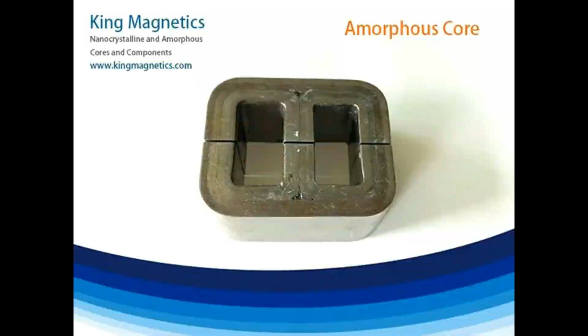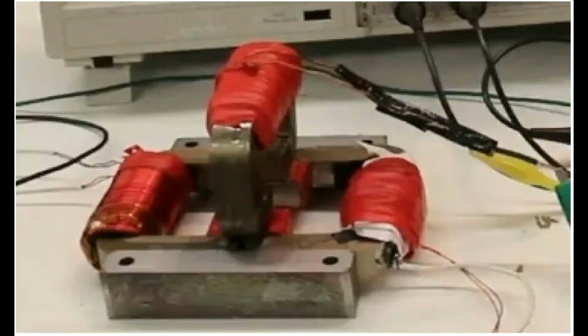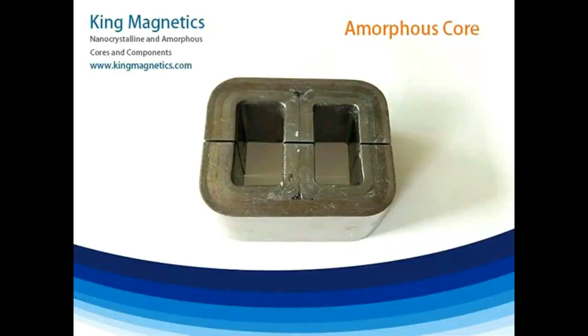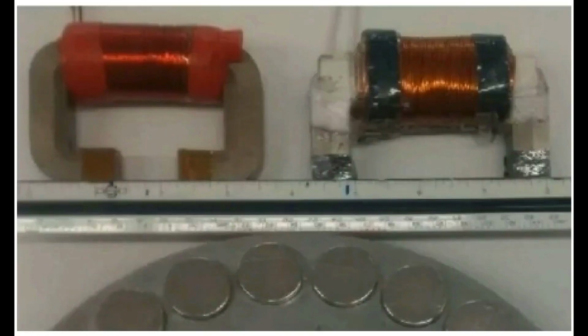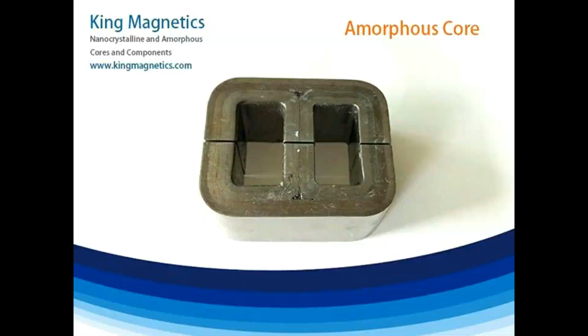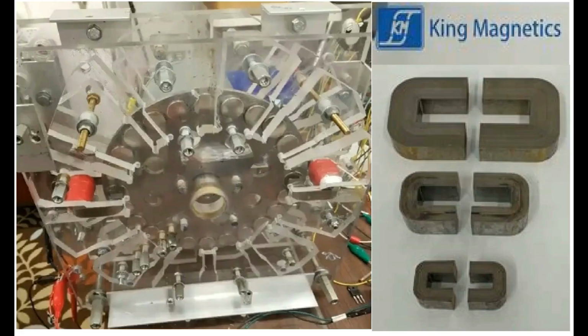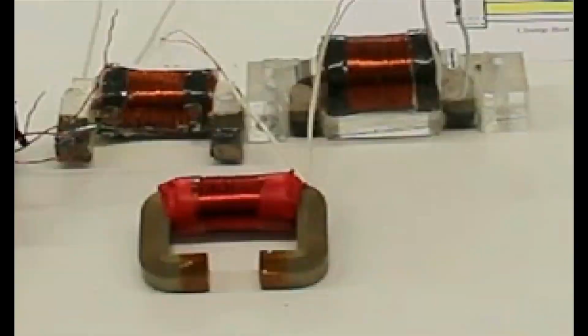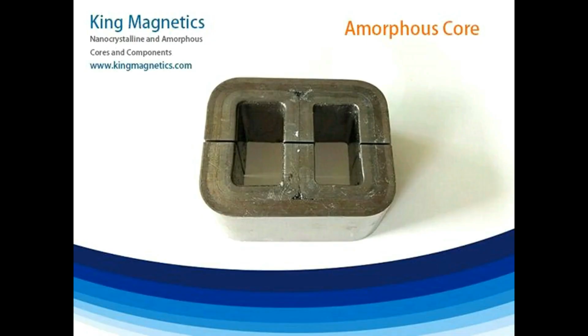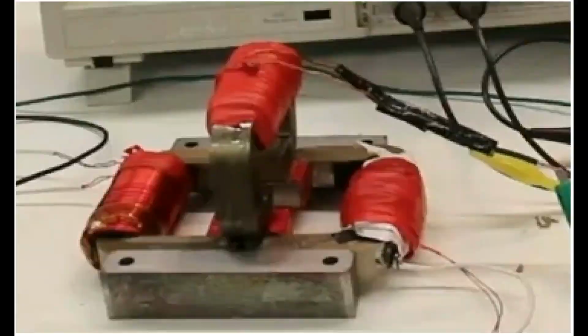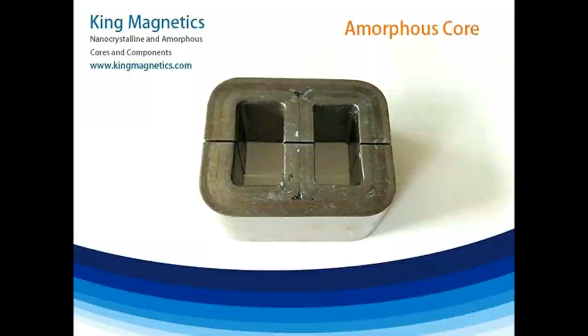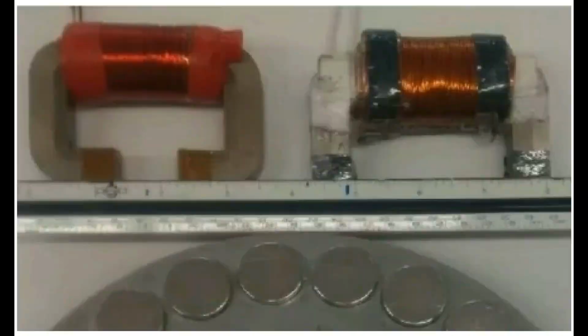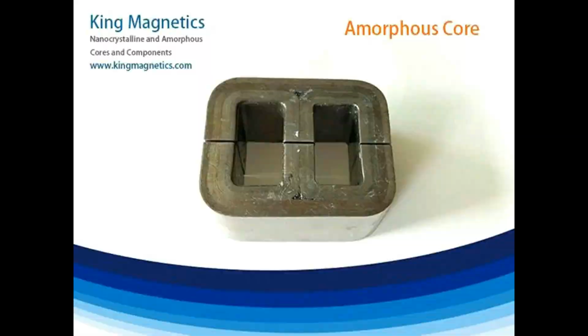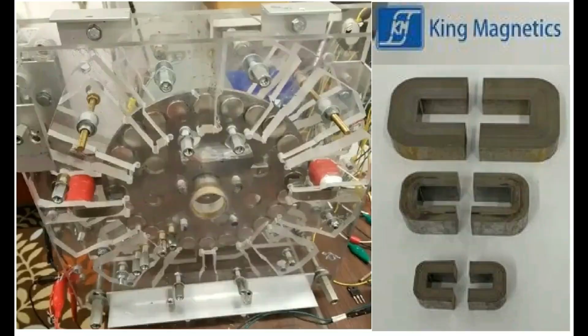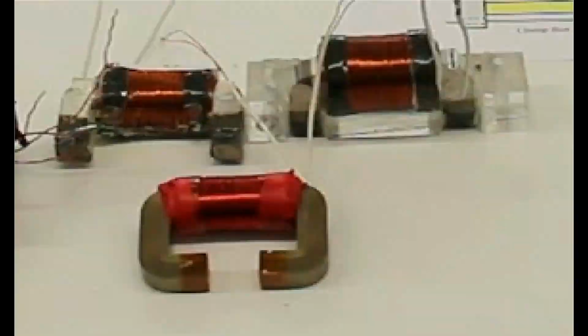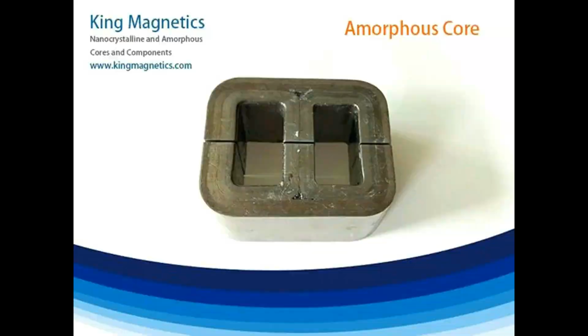An amorphous metal transformer is a type of energy-efficient transformer found on electric grids. The magnetic core of this transformer is made with a ferromagnetic amorphous metal. The typical material, Metglas, is an alloy of iron with boron, silicon, and phosphorus in the form of thin, for example 25 micrometers, foils rapidly cooled from melt. These materials have high magnetic susceptibility, very low coercivity and high electrical resistance. The high resistance and thin foils lead to low losses by eddy currents when subjected to alternating magnetic fields.